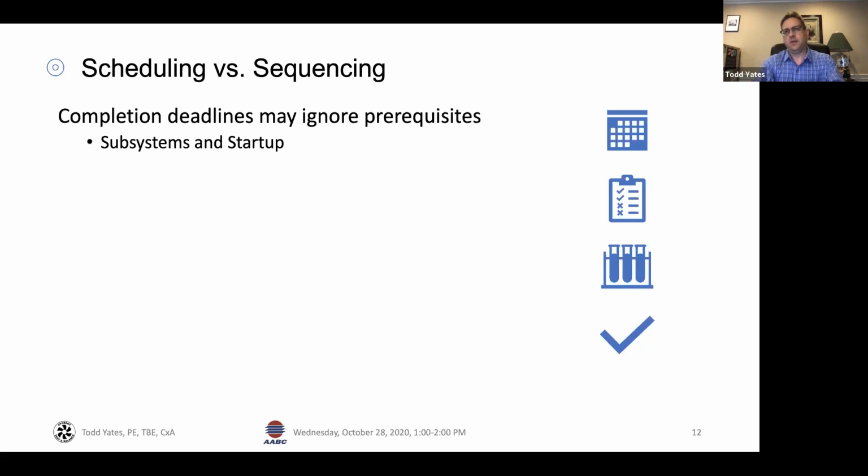And people will say, well, the air handler started. Can't we get test and balance here? Well, the air handler's been bumped. It can run in hand, but none of the VAVs are programmed. Things of that nature. We've done a piece of the startup, so start test and balance. Well, by integrating early and with the commissioning process, we can get these ideas out there on the floor so that people understand what the needs really are and how we go about doing that.